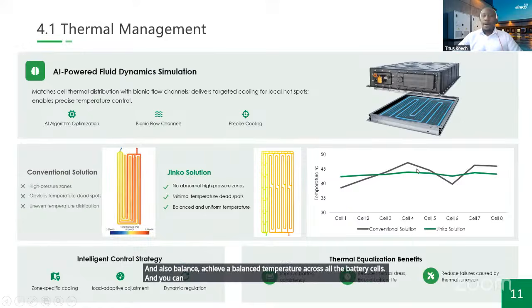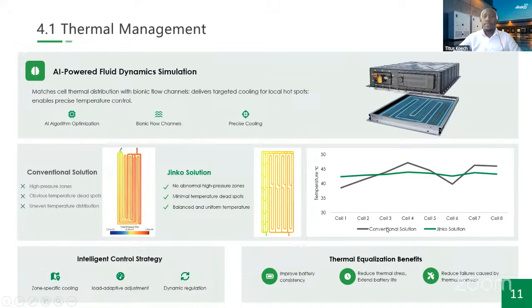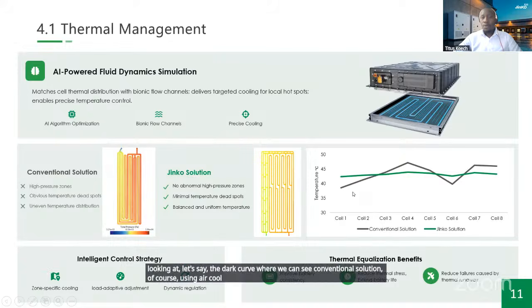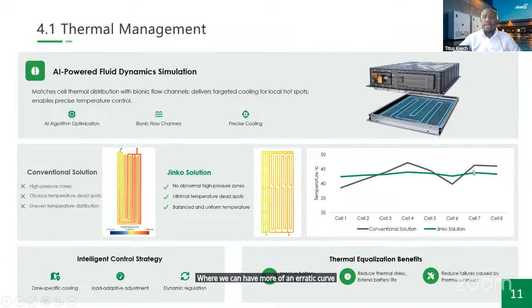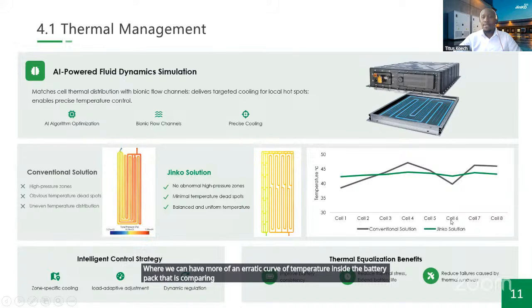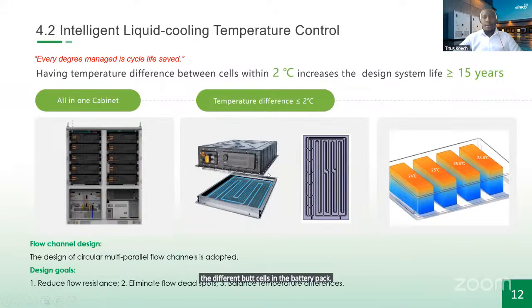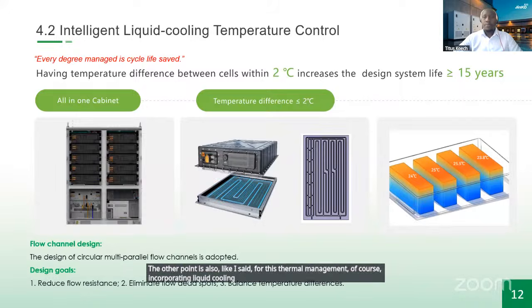Based on our own analysis, we can see optimal temperature control. Looking at the dark curve representing conventional air-cooled solutions, we see a more erratic temperature pattern across different battery cells, compared to the current liquid-cooled solution, which shows uniform, almost constant temperatures across the battery cells. Incorporating liquid cooling maintains a high degree of cooling and increases the overall system design life.